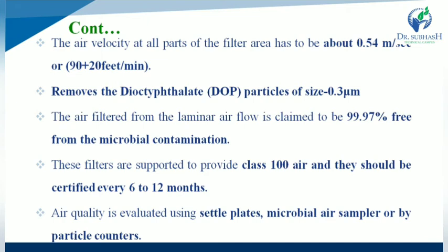Next one is, these filters are supported to provide class 100 air and they should be certified every 6 to 12 months. While air quality is evaluated using settle plates, microbial air samples or a particle counter.